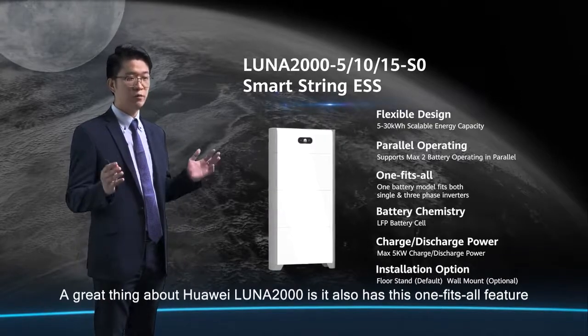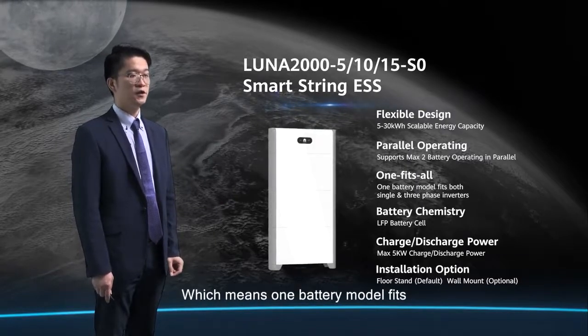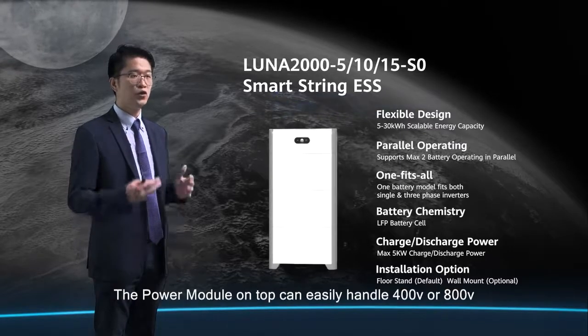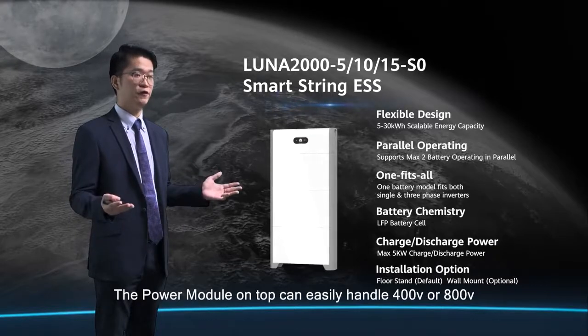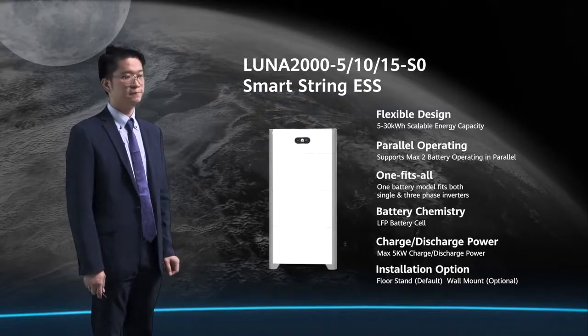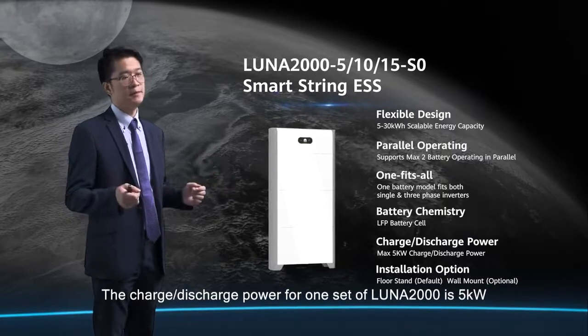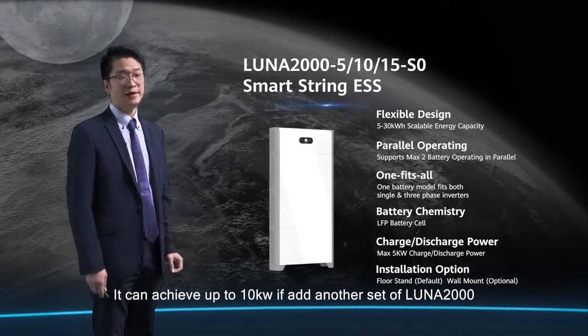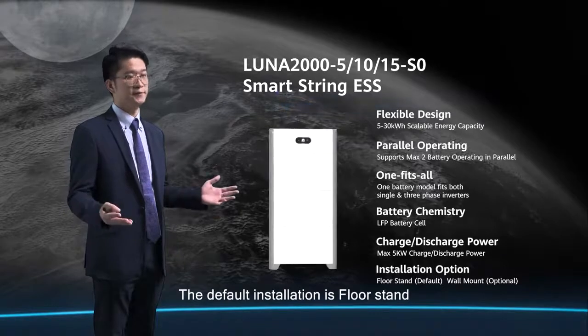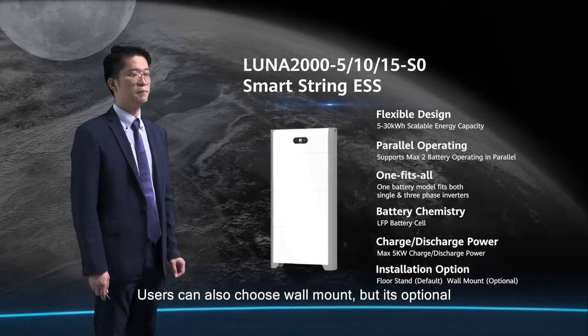A great thing about Huawei LUNA2000 is its one-fits-all feature, meaning one battery model fits Huawei's single-phase and three-phase inverters simultaneously. The power module on top can handle 400V or 800V high-DC voltage coupled systems. The battery chemistry is lithium-iron phosphate. The charge and discharge power of one set of LUNA2000 is 5 kW, and it can achieve up to 10 kW with two sets. The default installation is floor stand, with relevant parts included in the package. Wall mount is also available as an optional.